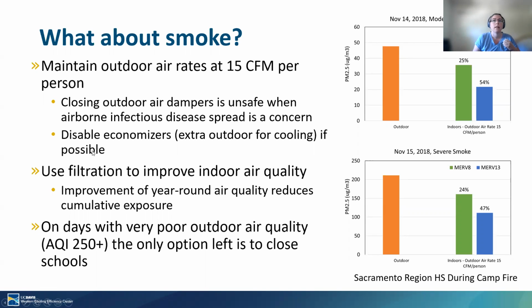An economizer, what an economizer does is when it's cool outside and the building is calling for cooling, it will open the outdoor air rate up to 100%. And that's great from an infectious disease perspective, but not if it's really smoky outside. So if possible, school districts disabling their economizers is a good idea, but sometimes you have to go into each and every unit, so it may be impractical.